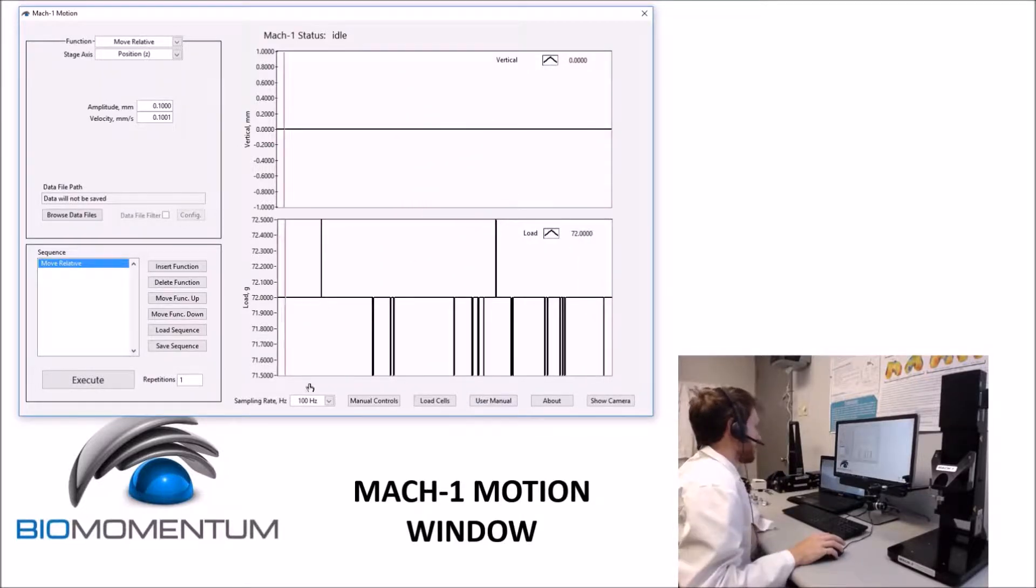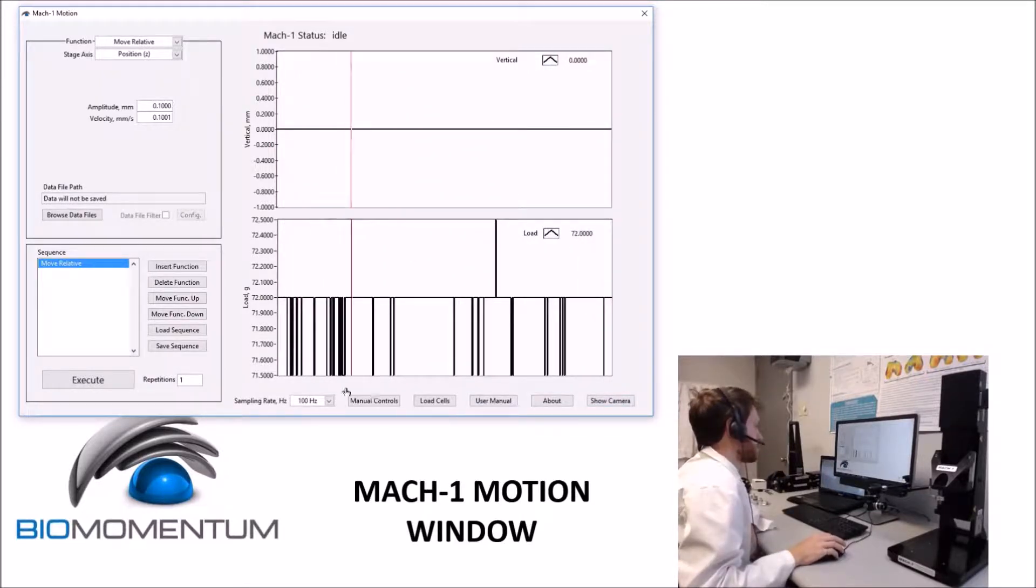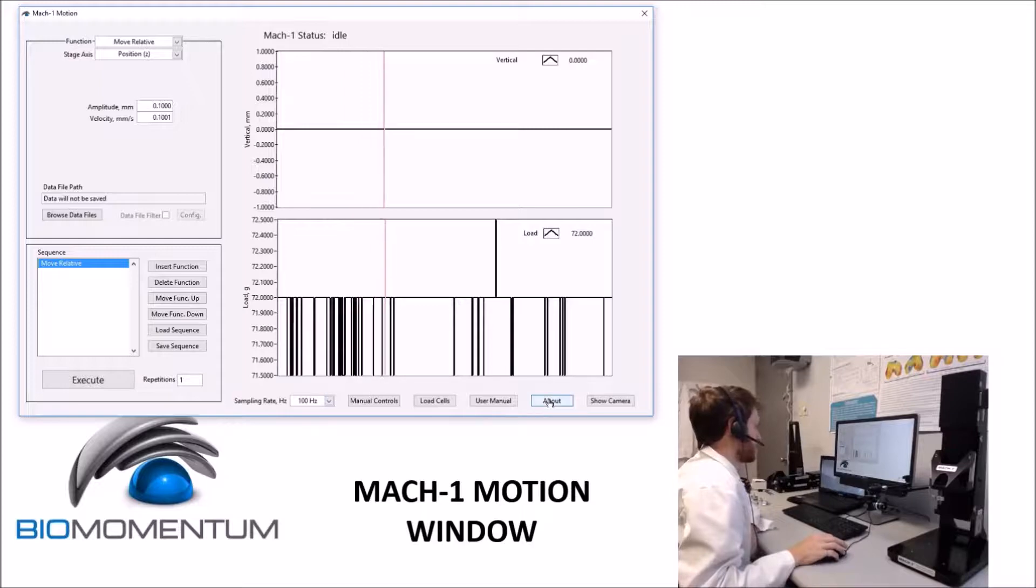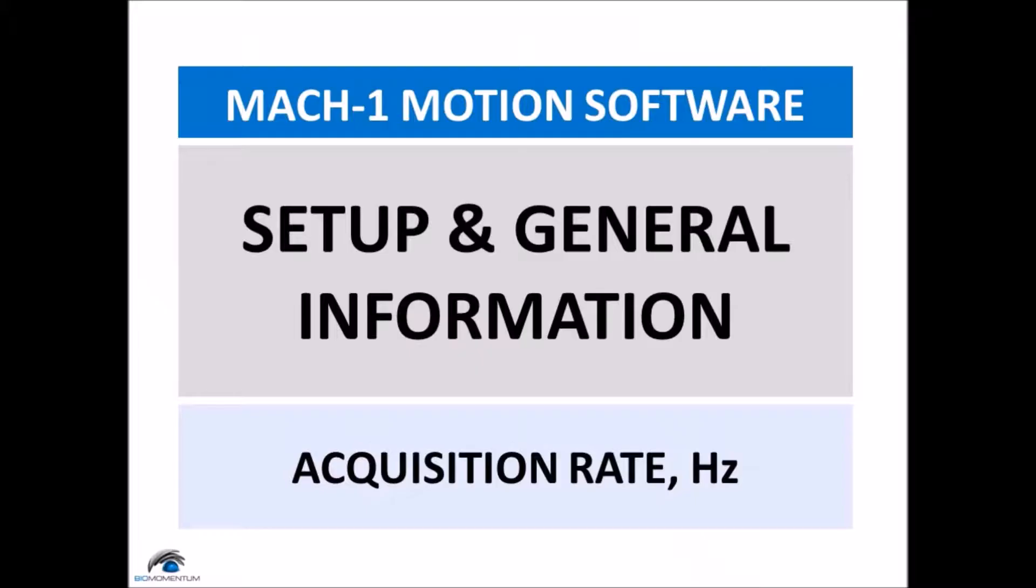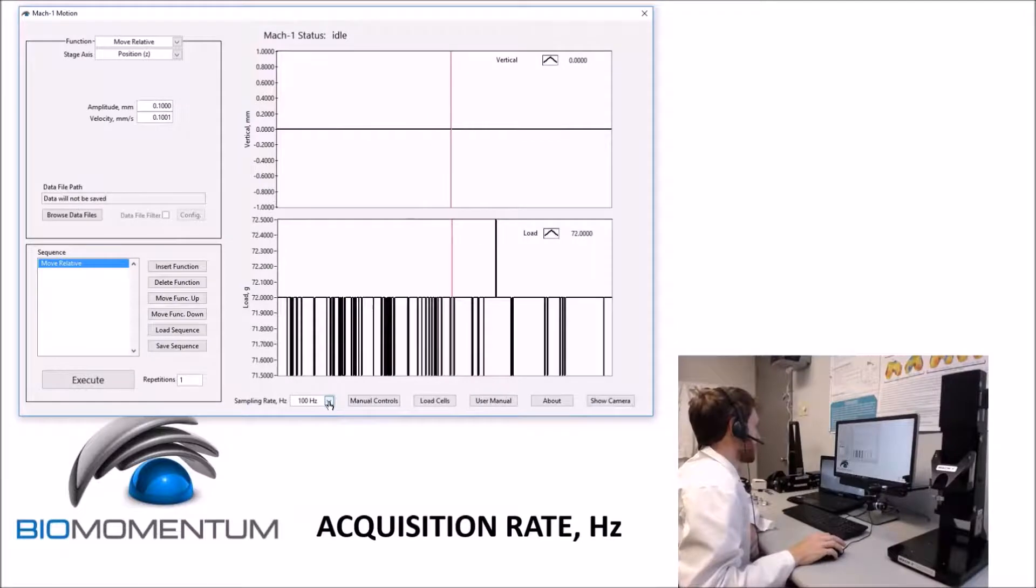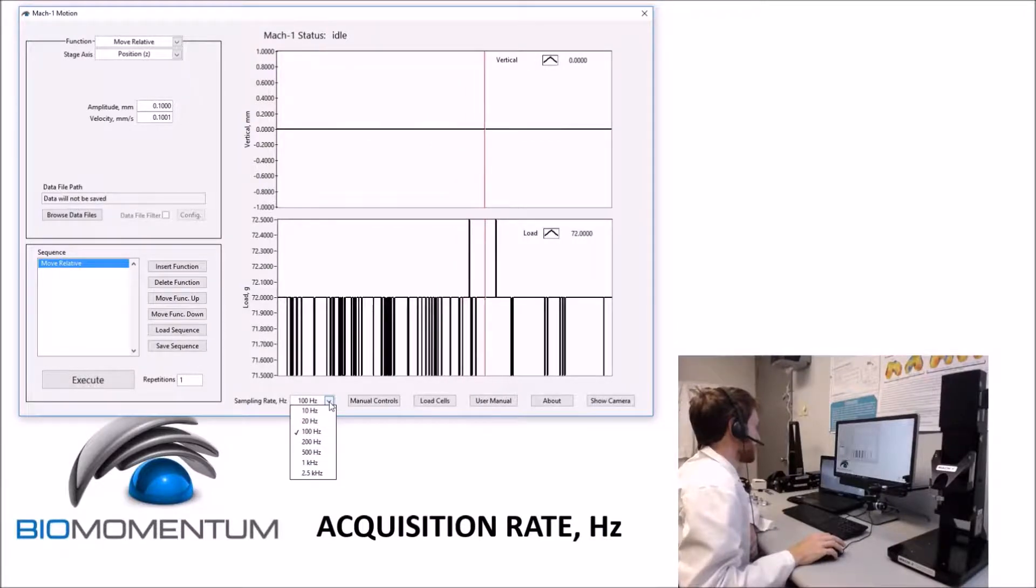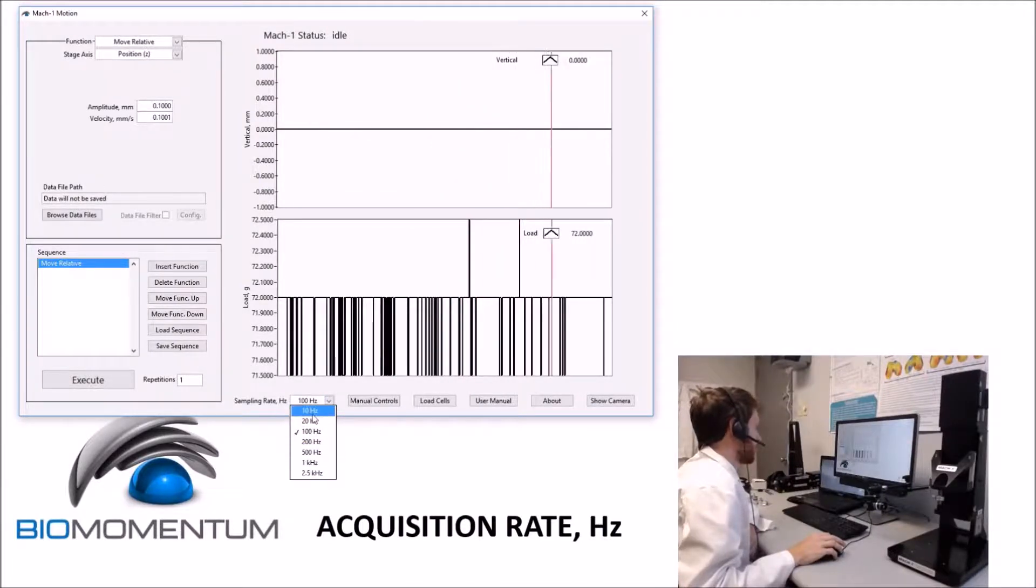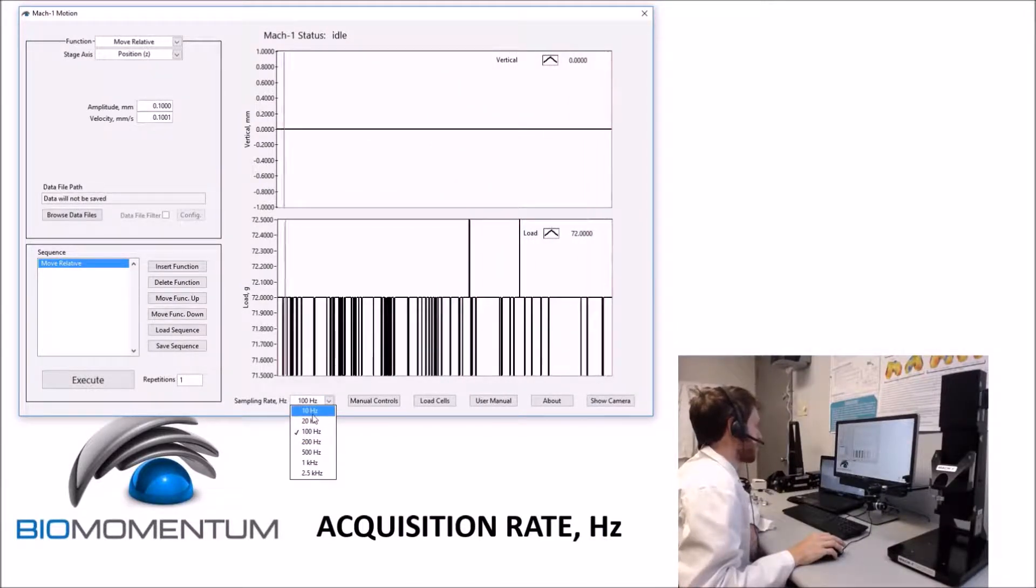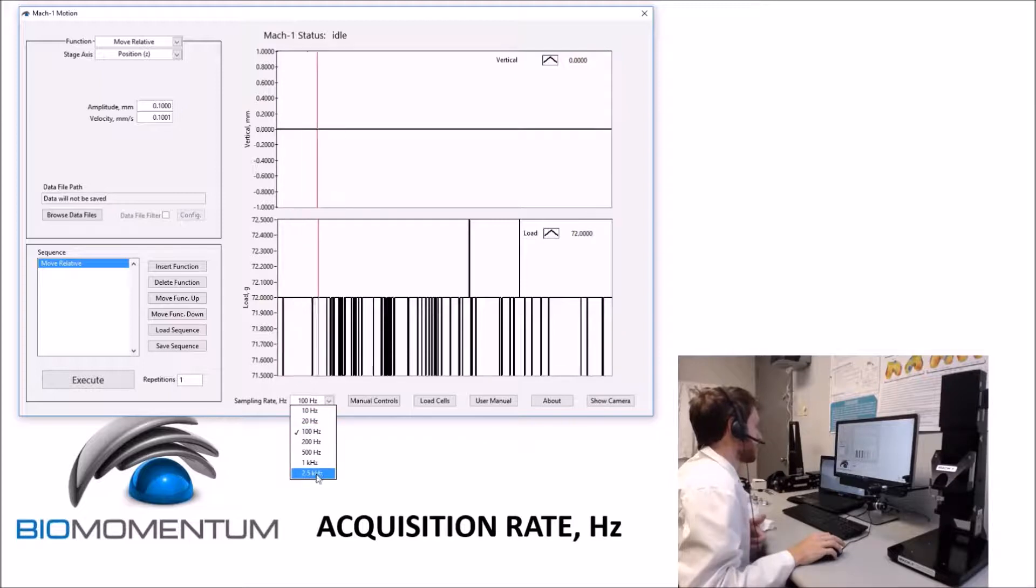The lower configuration panel consists of setup options as well as general information. The sampling rate determines the rate at which data is acquired, and eight different sampling rates are available. The higher rates will create larger data files.